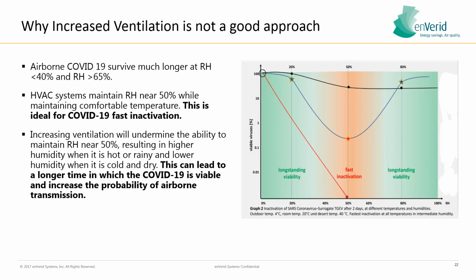So what's the best thing you can do? Obviously, controlling humidity within the space, keeping relative humidity near 50% while maintaining comfortable temperatures, is ideal for fast COVID inactivation. So if you're bringing in less outside air, in theory, your system should be able to handle keeping relative humidity at 50% more easily, because you're not potentially bringing in wet, damp, humid outside air.